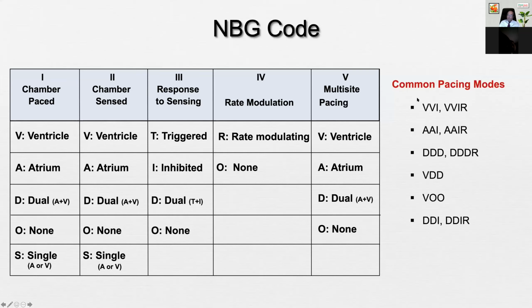Now on the right side, we have common pacing modes. VVI is a very commonly used pacemaker still in our countries, and VVI means the first letter V means ventricle paced, second letter ventricle sensed, and third is inhibited. So it's in demand mode. The fourth letter could sometimes be present, which is VVIR, which would mean that the pacemaker is rate responsive, which means it has a sensor inside it, which can sense the patient's activity and increase the heart rate accordingly. And the second common mode is AAI or AAIR.